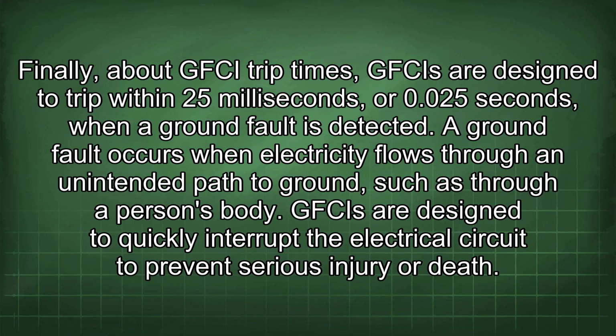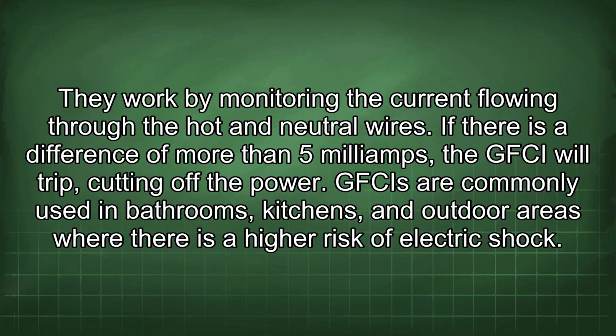Finally, about GFCI trip times. GFCIs are designed to trip within 25 milliseconds, or 0.025 seconds, when a ground fault is detected. A ground fault occurs when electricity flows through an unintended path to ground, such as through a person's body. GFCIs are designed to quickly interrupt the electrical circuit to prevent serious injury or death. They work by monitoring the current flowing through the hot and neutral wires. If there is a difference of more than 5 milliamps, the GFCI will trip, cutting off the power.